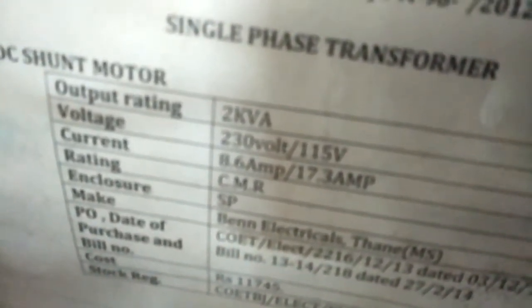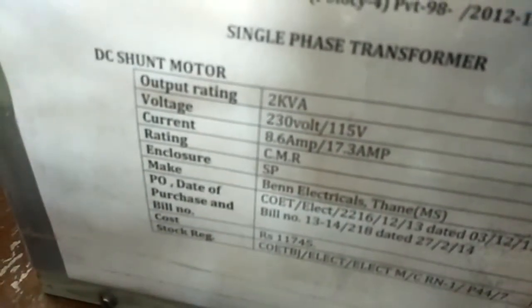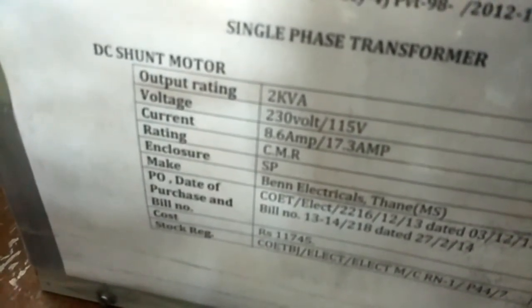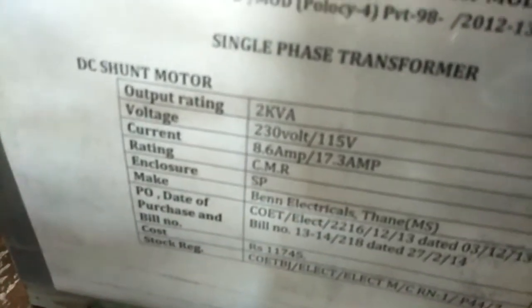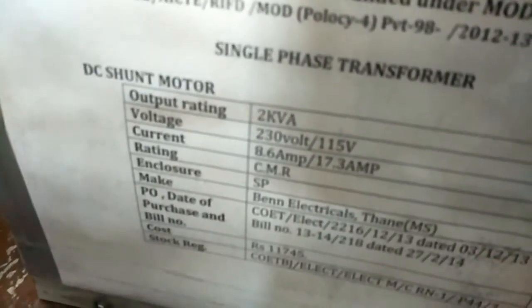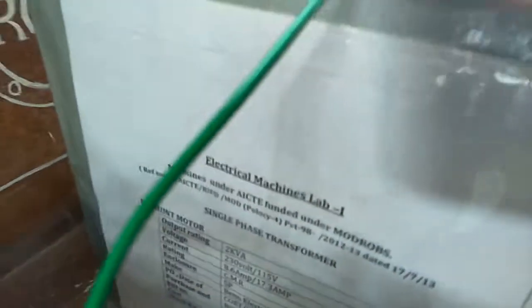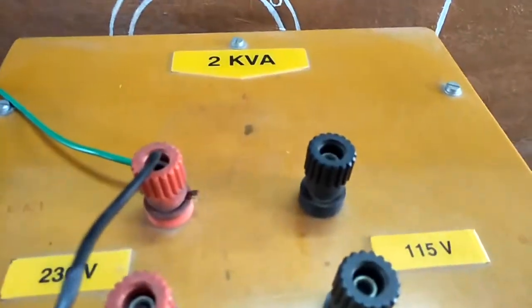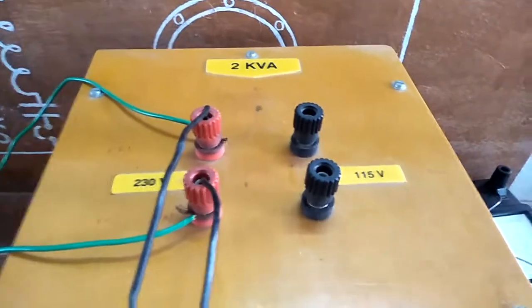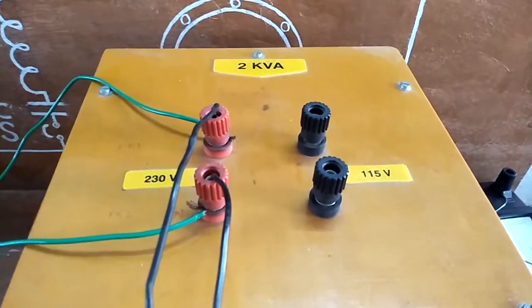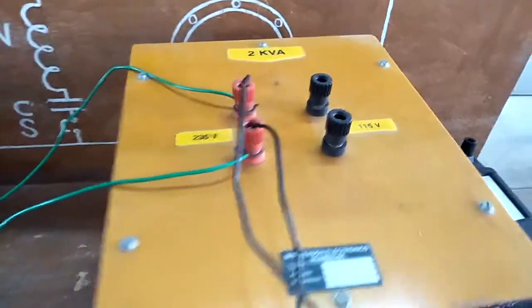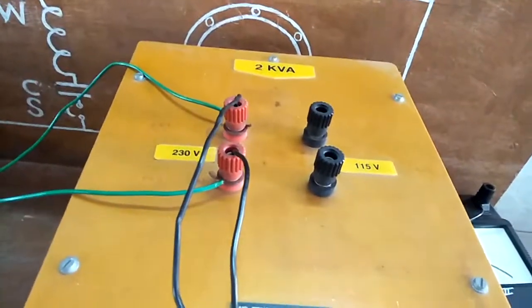Now if you see the rating of the transformer, it is 230 by 115, 2 kVA. 8.6 ampere is the primary current, and on the LV side it is 17.3 ampere, the secondary current. So on the HV side it is 8.6 ampere at full load condition, whereas the secondary current, because the secondary voltage is 115, it is the LV side, so it has only 17.3 ampere.